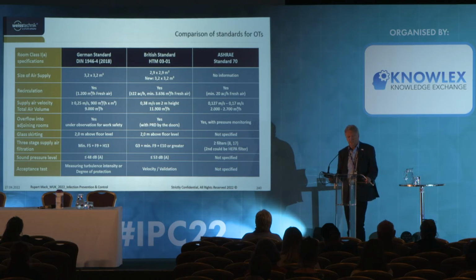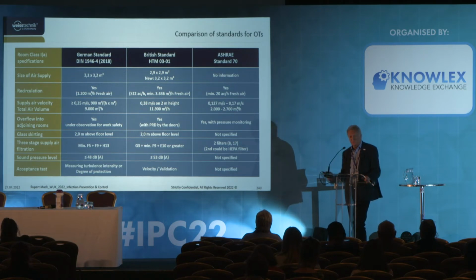The different standards have big differences between them. This table shows the German standard compared to the UK standard, as well as the ASHRAE Standard 170. It shows there's a big difference between air volume flows. So the question is, what is the right air volume flow?